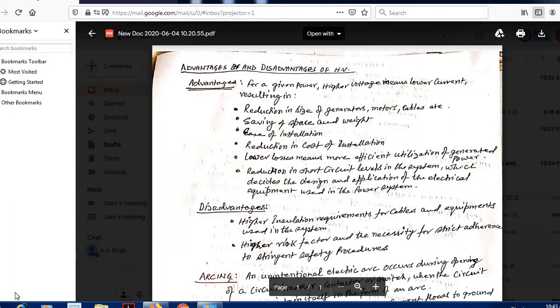Now the advantage of this high voltage system is, first of all, we never wanted to go for high voltage because of its hazard. But we had no option but to go for high voltage because we could not manage with 440 volt or low voltage systems, because the power is increasing day by day. Why did we go for high voltage? Because the current was high for the higher rated power, and if I allow that current to pass, it causes more I square R loss, more heat generation, causing the insulation temperature to rise. If it rises above the safe working temperature of the insulation class, there will be a failure of insulation, leading to short circuit and burning of the motor.